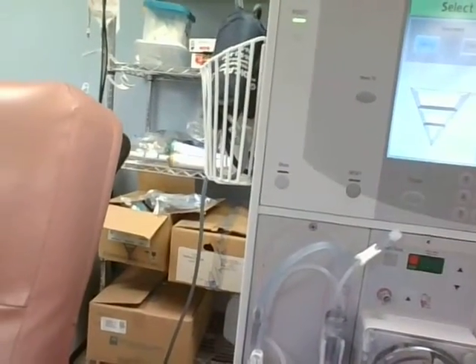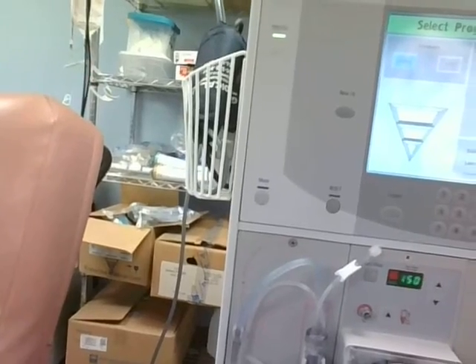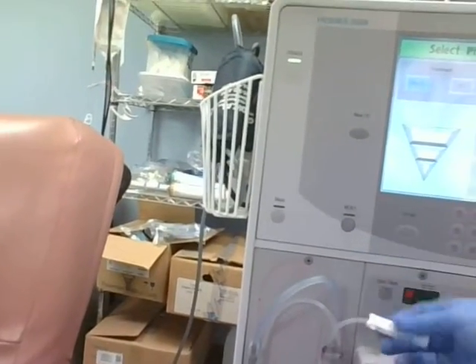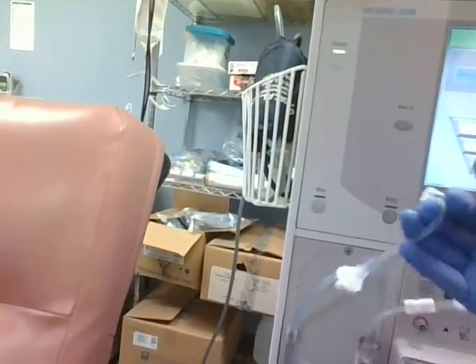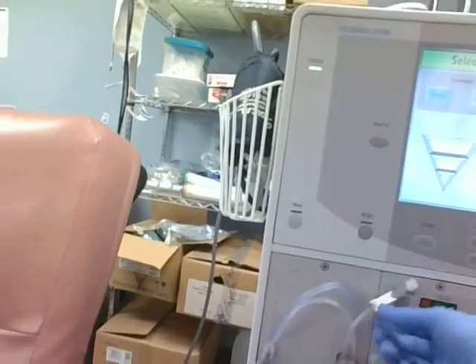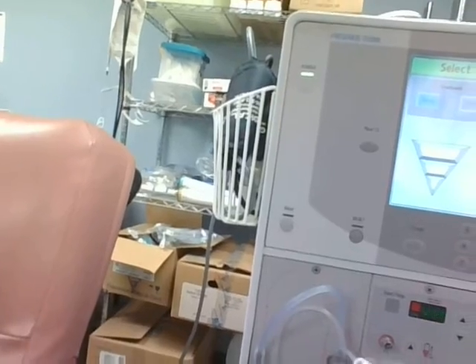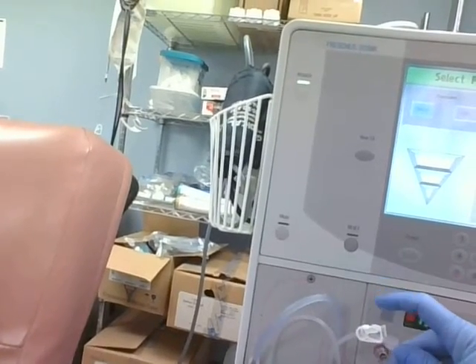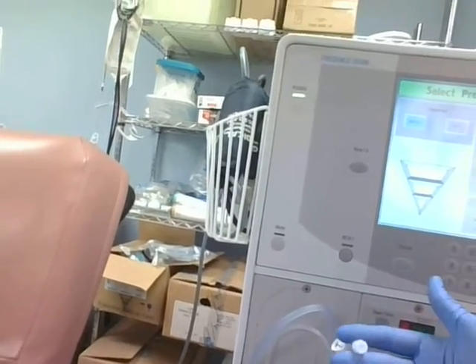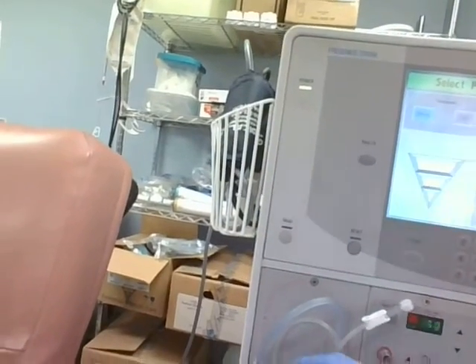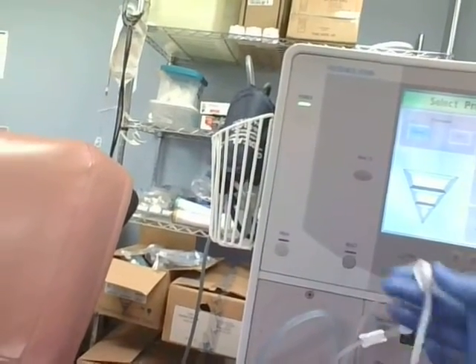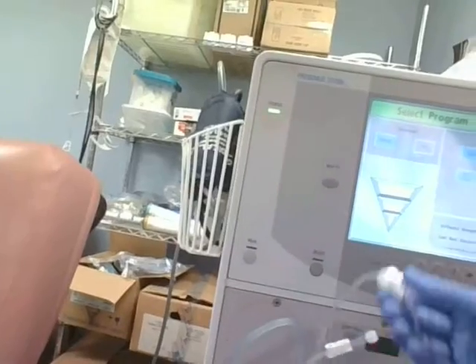So now what we're going to do is we're going to fill up our drip chamber here. Okay, so there are two ways you can do this. I prefer to use the transducer protector line because on this line it's a double. If I were to use my medication line, I have to unclamp here and take the cap off. And if I use my transducer protector line, I only have to unclamp.